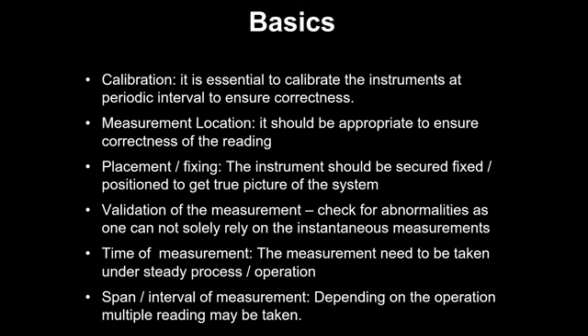So calibration is essential to validate that the reading we are getting is correct, and that our instrument doesn't have any fault. The audit is the exercise based on which the client is going to take major decisions about investment changes. If our readings are not correct and what we suggest is based on erroneous data, then ultimately it is going to land the client in a problem, because after the modification the system doesn't work properly, and it's going to be a financial loss for him.